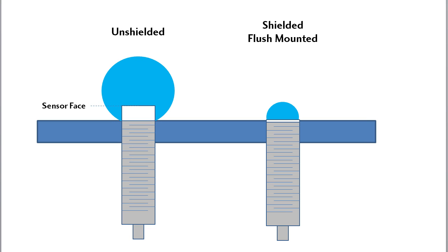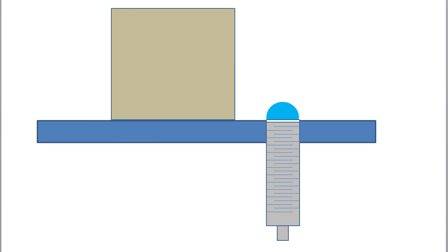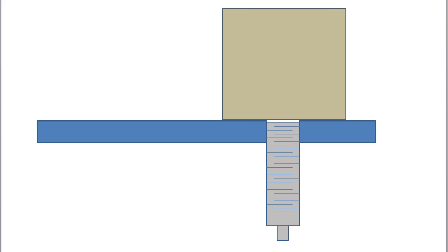So when you flush mount one of these in a metal bracket, you are actually choking out a portion of the sensing region and reducing the range. That's usually not a big deal because if you are flush mounting a sensor it's probably because the object is sliding right over the sensor so distance isn't a big issue.